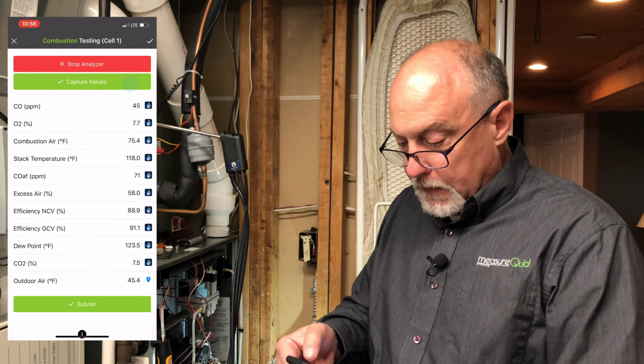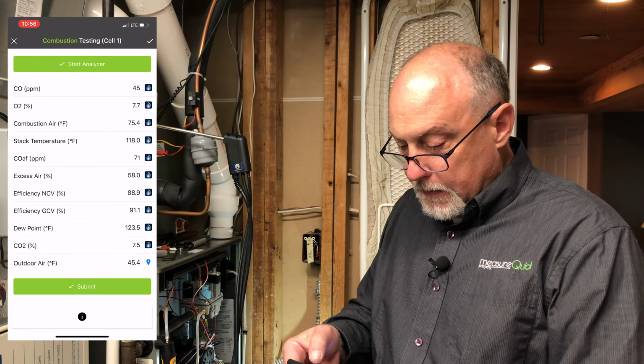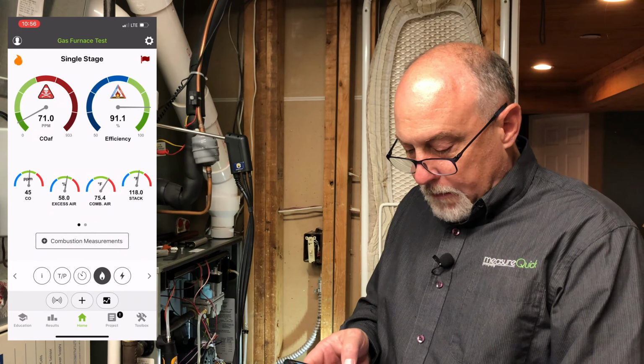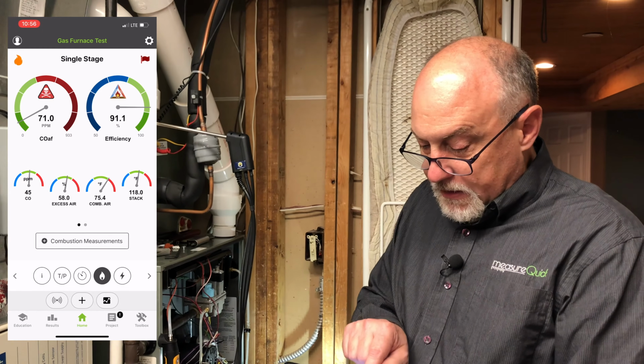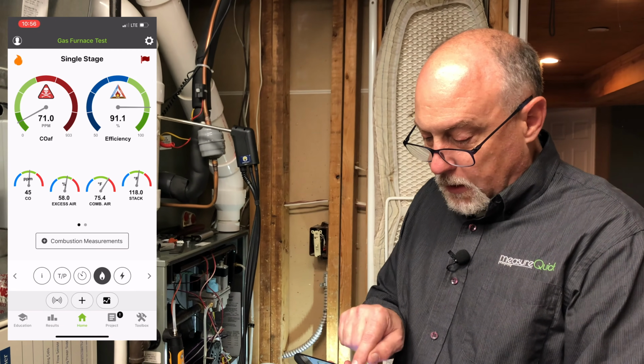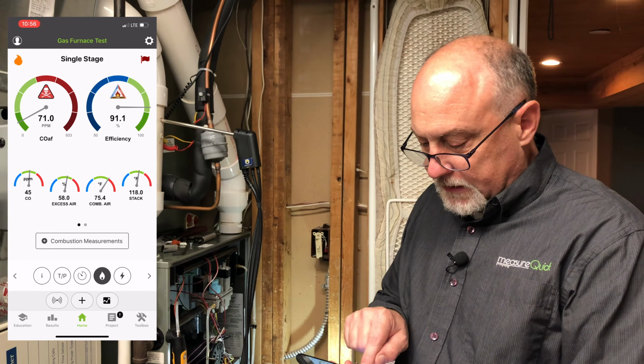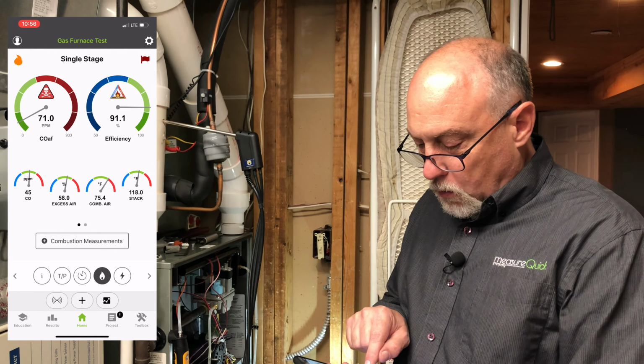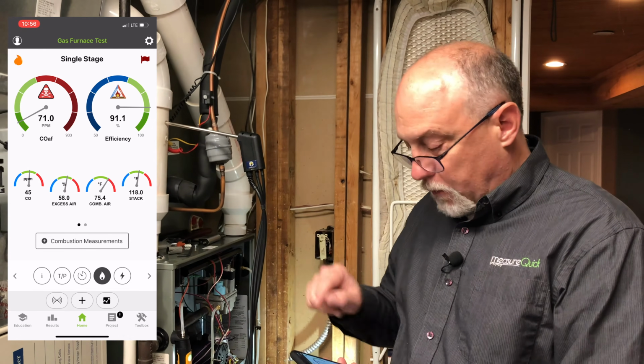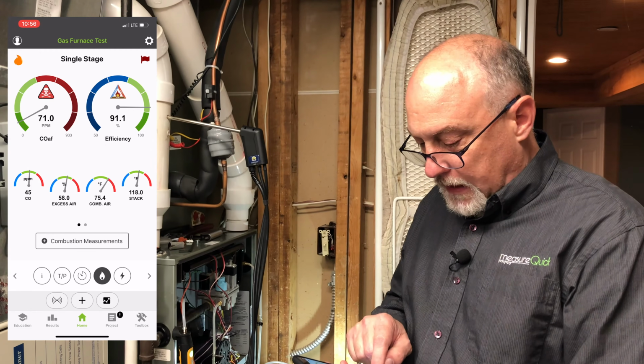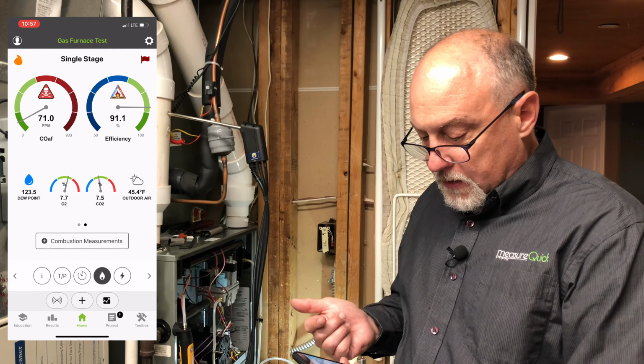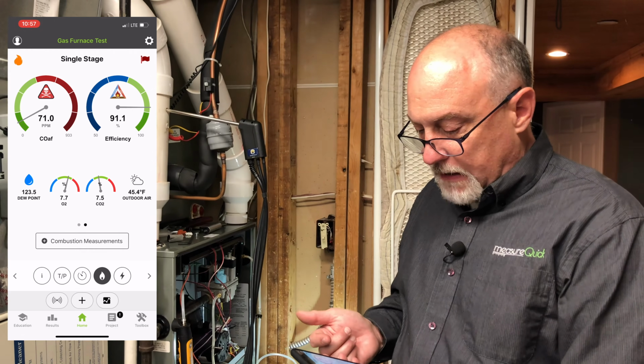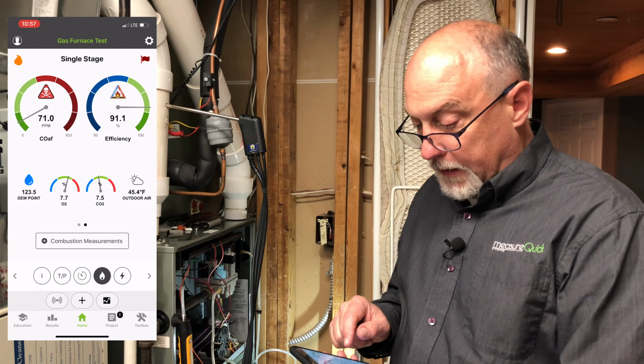Everything looks good. I'm going to capture my values and then hit submit. Now I'll scroll through these real quick. I can see my CO is in a safe range, CO air-free, combustion efficiency looks good, excess air looks good. Combustion air temperature is a little warm because we're pulling air in from the room instead of from outside. Let me tap this over, my O2 is at 7.7, CO2 is at 7.5. All those readings look good on the analyzer.